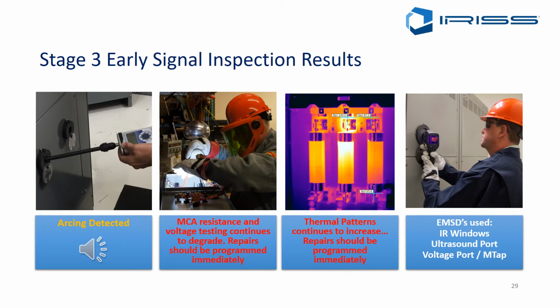At this stage, we'll probably pick up something called arcing. This is the final stage of electrical failure, and if you hear arcing, that's critical. You would shut down immediately. You wouldn't even open this panel at all. It's just far too dangerous. And arcing sounds like this.